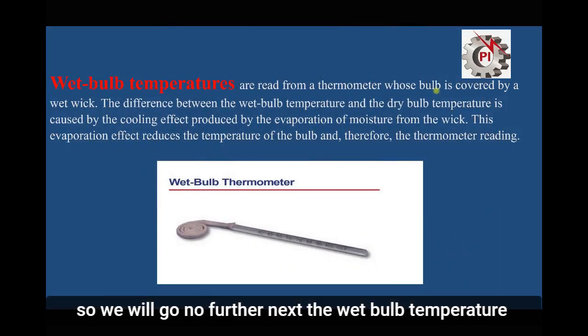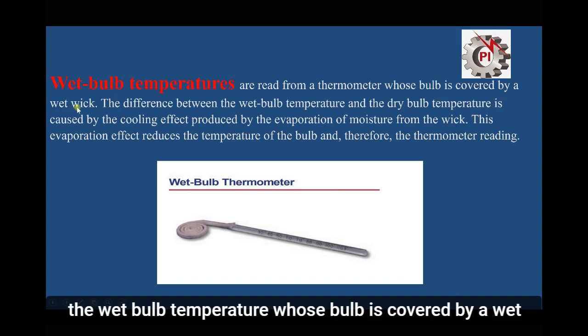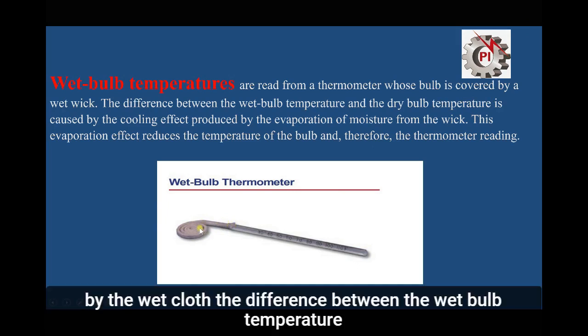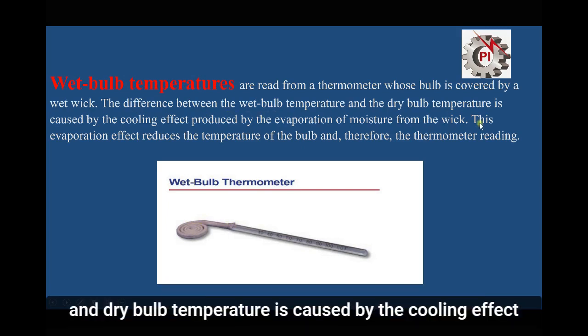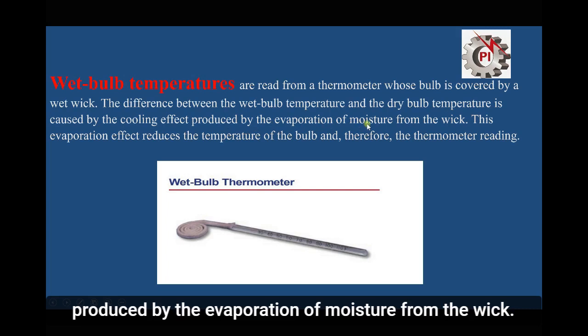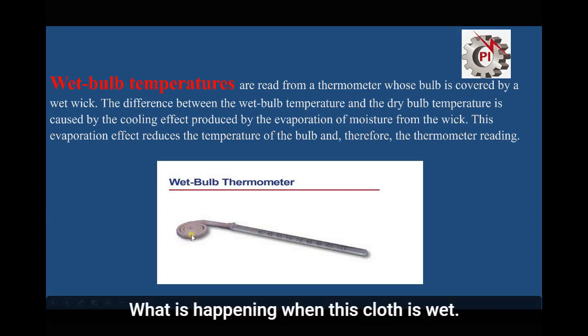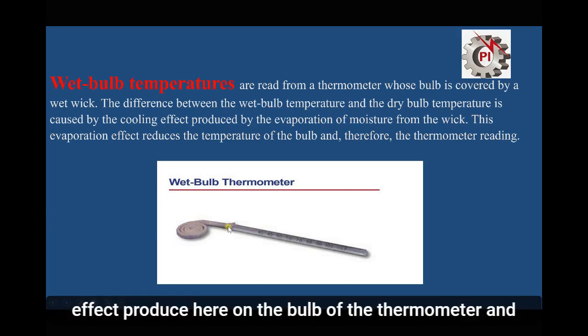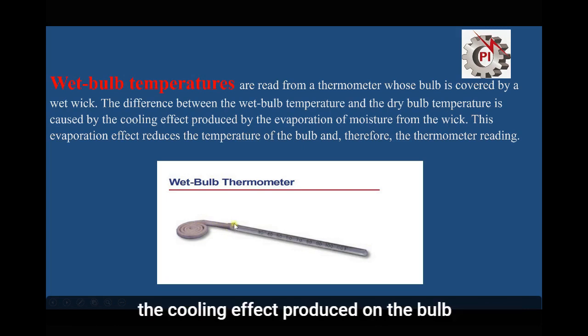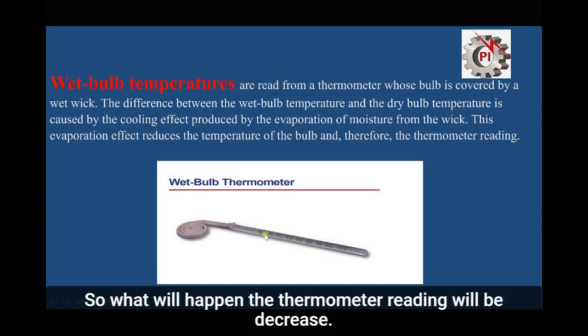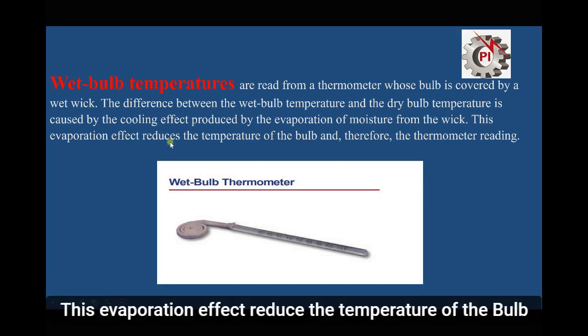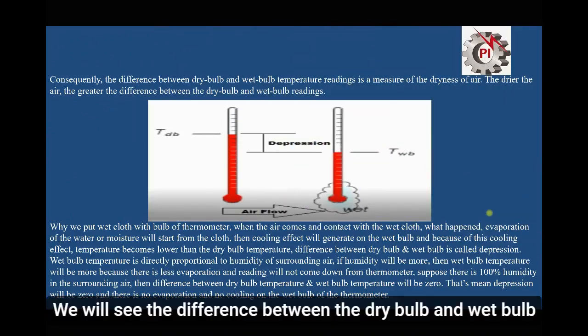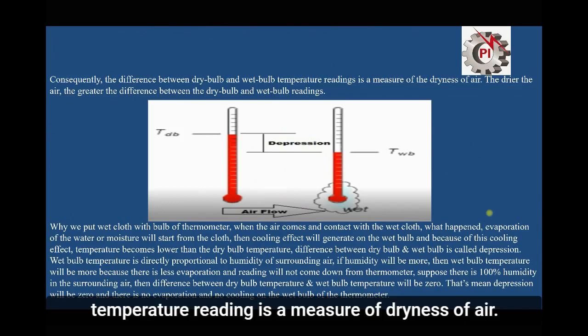The wet bulb temperature uses a thermometer whose bulb is covered by a wet wick — a wet cloth. The difference between the wet bulb temperature and dry bulb temperature is caused by the cooling effect produced by the evaporation of moisture from the wick. When the cloth is wet and evaporation starts, a cooling effect is produced on the bulb of the thermometer, which reduces the thermometer reading.